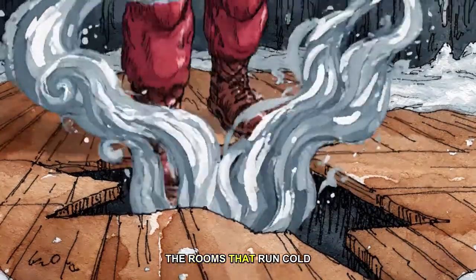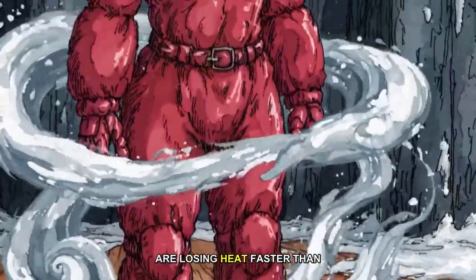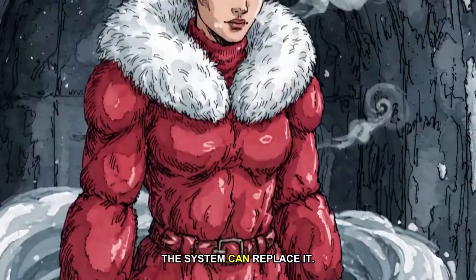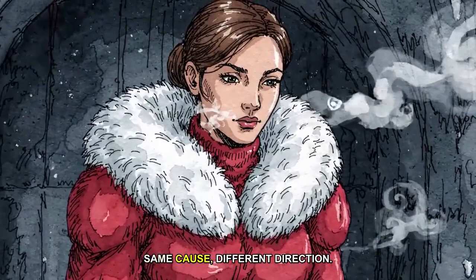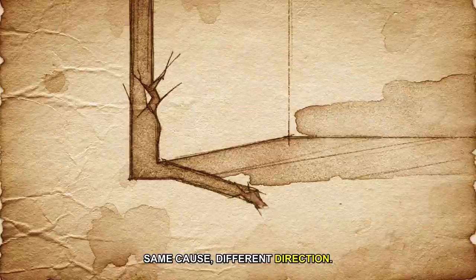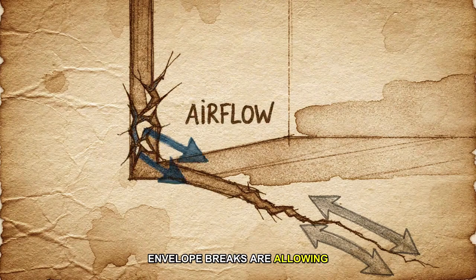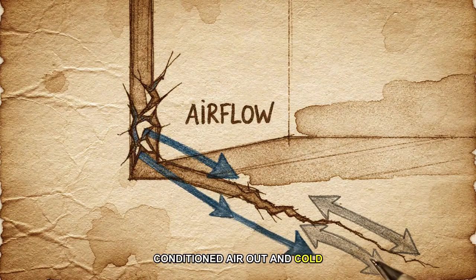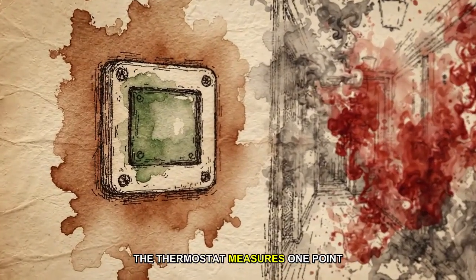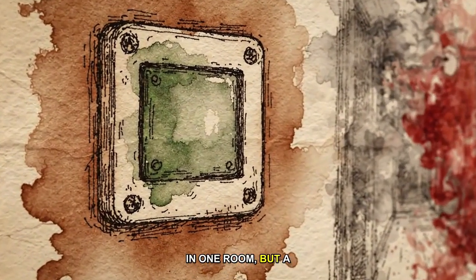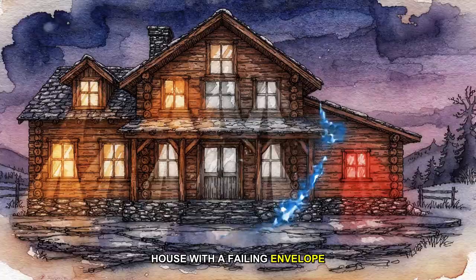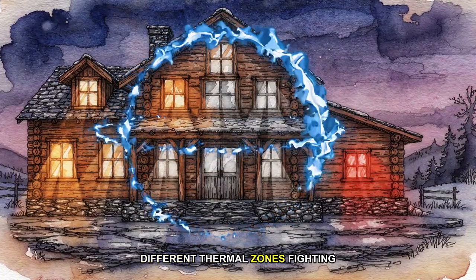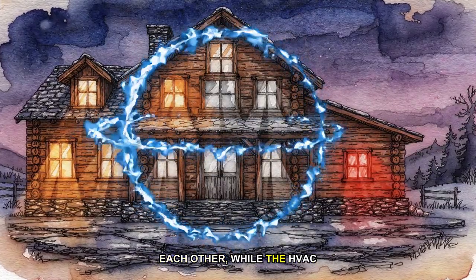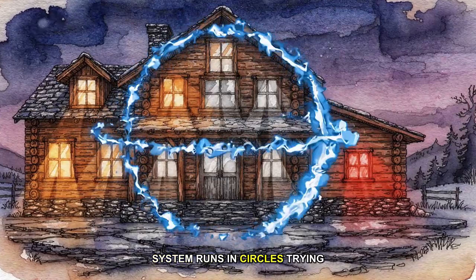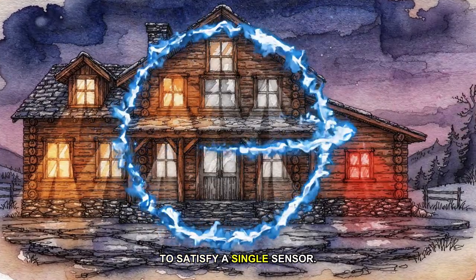The rooms that run cold are losing heat faster than the system can replace it. Same cause, different direction. Envelope breaks are allowing conditioned air out and cold air in. The thermostat measures 1 point in one room, but a house with a failing envelope has 10 different thermal zones fighting each other, while the HVAC system runs in circles trying to satisfy a single sensor.